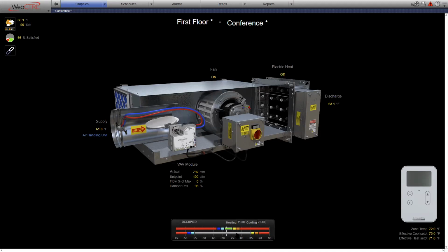Now, one of the things Automated Logic developed a number of years ago was a way of doing demand control. It was studied by Lawrence Berkeley National Laboratories. It allows, in response to demand in a building, these set points to float and expand as a way of curtailing demand in non-critical zones. So if you've got a building with 400 zones in it, and you take all of those cooling set points and raise them by, say, half a degree, you're going to reduce demand. Fans are going to keep going. You're still going to have airflow, but you're definitely going to reduce demand.